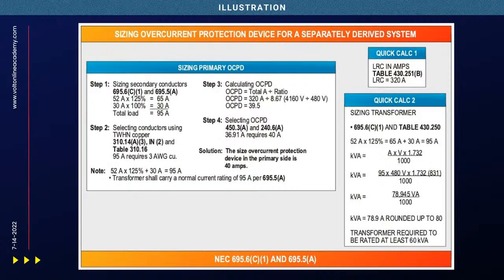So I'm going to take that 95 amps. The secondary side voltage was 480 volt 3-phase, so that'd be 831 once I multiply 480 by 1.732, then divide 1,000 into that, giving me 78.9 kVA. Then I round up, and that tells me the transformer is required to be rated at least 80 kVA.